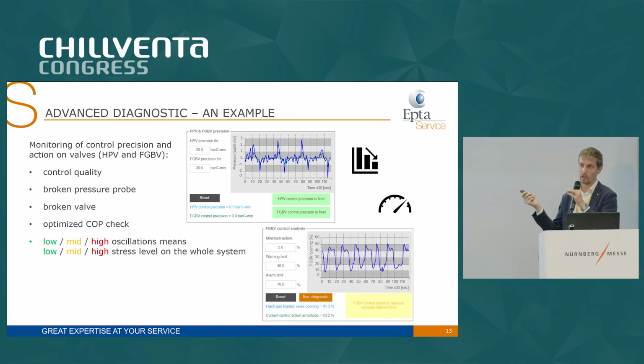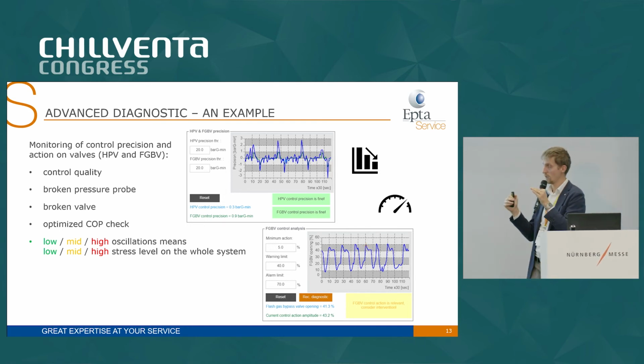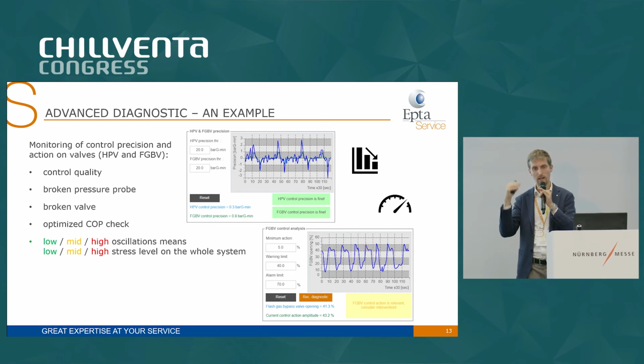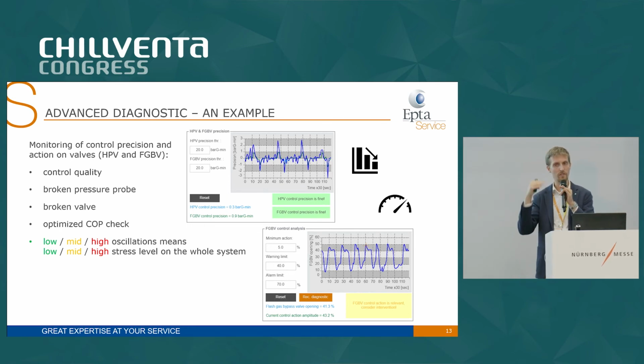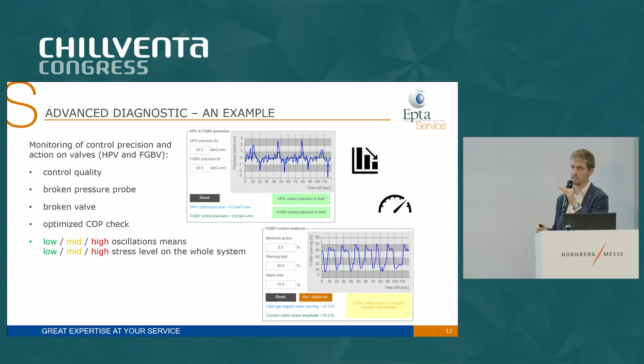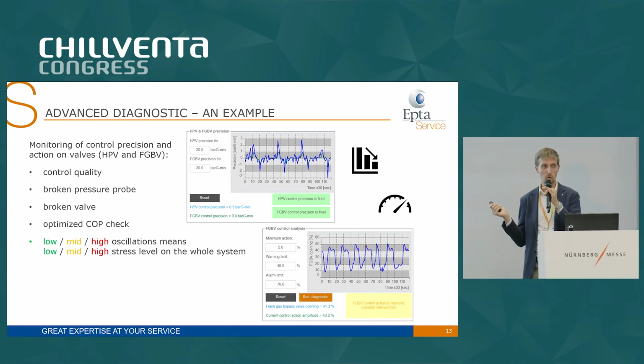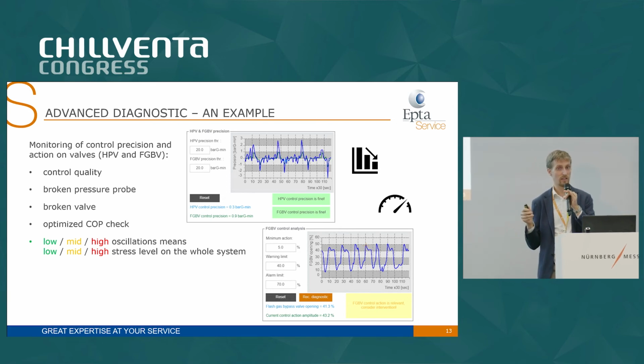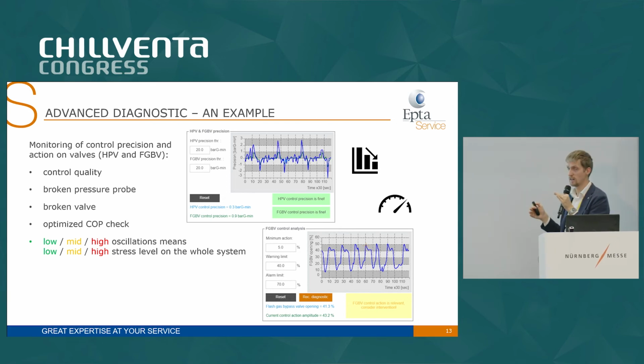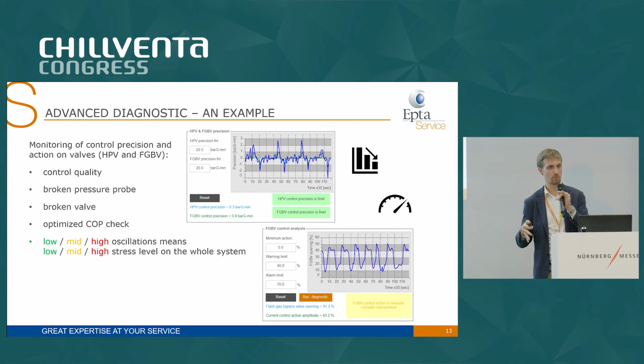Another example of algorithm: the calculation over a certain amount of time, in this case a couple of hours, of the maximum minus minimum opening of the valve. If this value is higher than a certain threshold, in this case 40% and another limit of 70%, then a specific warning or alarm is triggered, saying we have these valves that are oscillating too much. Probably there is something wrong in a certain part of the system.